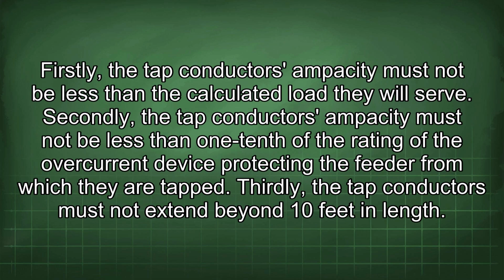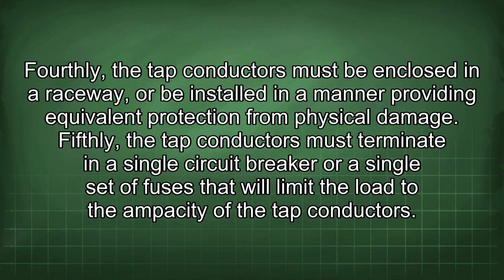Firstly, the tap conductor's ampacity must not be less than the calculated load they will serve. Secondly, the tap conductor's ampacity must not be less than 1/10 of the rating of the overcurrent device protecting the feeder from which they are tapped. Thirdly, the tap conductors must not extend beyond 10 feet in length. Fourthly, the tap conductors must be enclosed in a raceway or be installed in a manner providing equivalent protection from physical damage. Fifthly, the tap conductors must terminate in a single circuit breaker or a single set of fuses that will limit the load to the ampacity of the tap conductors.